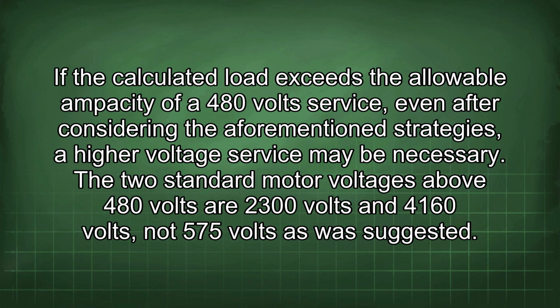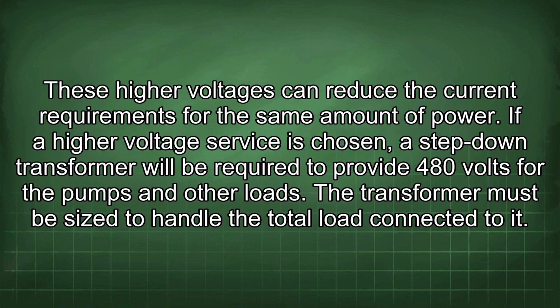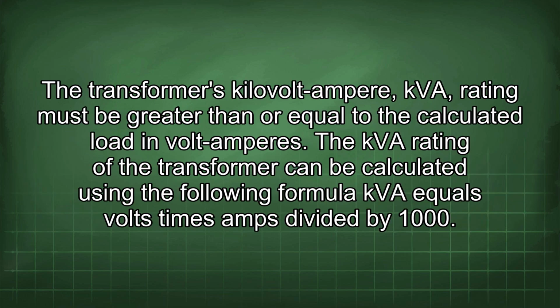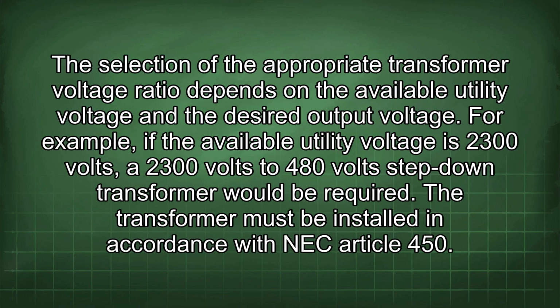The two standard motor voltages above 480 volts are 2300 volts and 4160 volts, not 575 volts as was suggested. These higher voltages can reduce the current requirements for the same amount of power. If a higher voltage service is chosen, a step-down transformer will be required to provide 480 volts for the pumps and other loads. The transformer must be sized to handle the total load connected to it. The transformer's kilovolt-ampere, kVA, rating must be greater than or equal to the calculated load in volt-amperes. The kVA rating of the transformer can be calculated using the following formula: kVA equals volts times amps divided by 1000. The selection of the appropriate transformer voltage ratio depends on the available utility voltage and the desired output voltage.